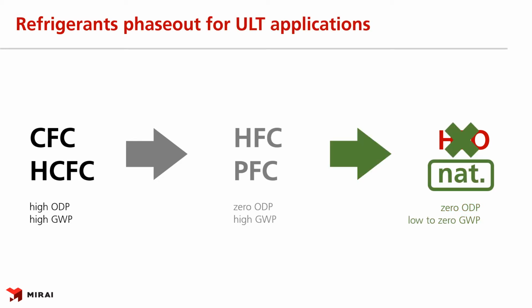Now, let's switch gears to the ultra-low temperature refrigerants. HFOs are a direct replacement for medium and low temp applications, therefore not suitable for ultra-low temperatures. And even so, HFOs still come with their own challenges, such as lubrication issues, reactions with some metals, and others. There is not a sufficient replacement portfolio built for ULT applications yet, hence the exception we touched on briefly before. And who knows, there might never be equal replacements to high GWP refrigerants used in applications below -40 degrees Celsius.